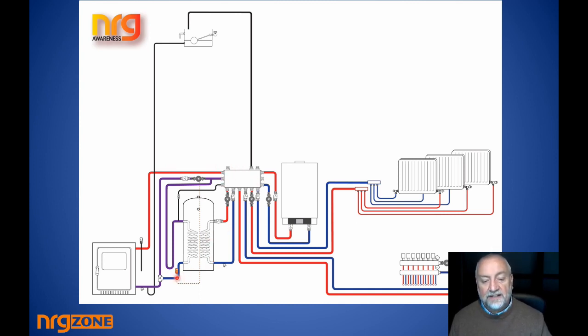The pipe stat that's located on the return from the cylinder is critical. It's set at 55 degrees. Why? It's set at 55 degrees on the return because you should never let water less than 55 degrees get into a stove if you can help it. Obviously there's a startup period and there's a cooling down period, but I'm saying that in the normal course of events you want to have it so that the pumps will draw the cold water back from the system only when the return going back to the stove can handle 55 degrees.